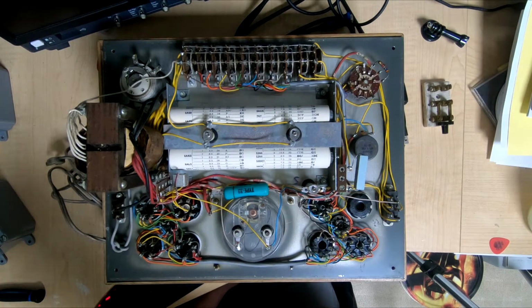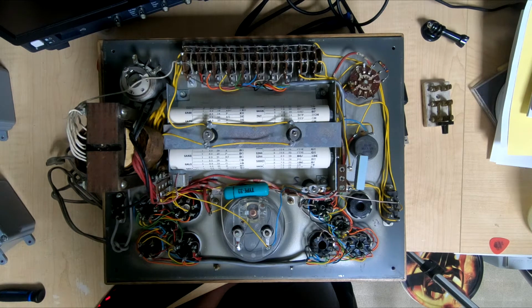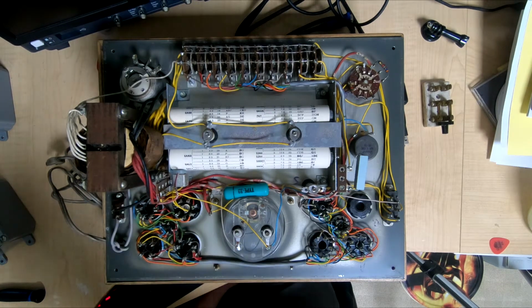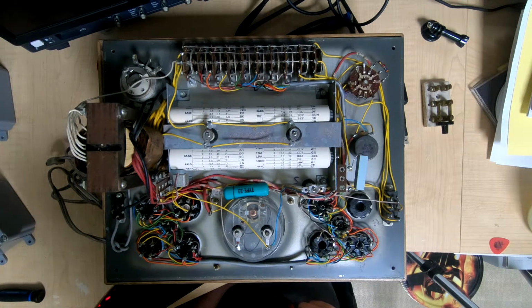The other component that is of concern maybe is this rectifier here. I did do a little bit of homework, and it should not be a selenium based rectifier, it should be copper oxide, but it's worth double checking to make sure it's working correctly and see whether it needs to be replaced.